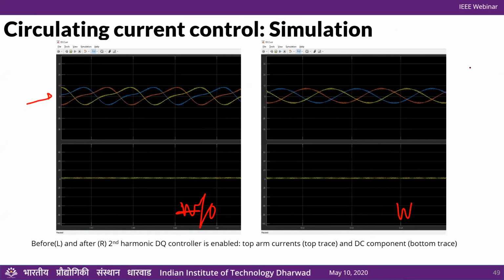You can see there's a significant amount of second harmonic flowing in all three. Just after I enable my circulating current control, the second harmonic is eliminated. In this particular system, the passives were sized such that this inherent second harmonic isn't that high. It's still there, but in magnitude terms it doesn't affect the total current by much.